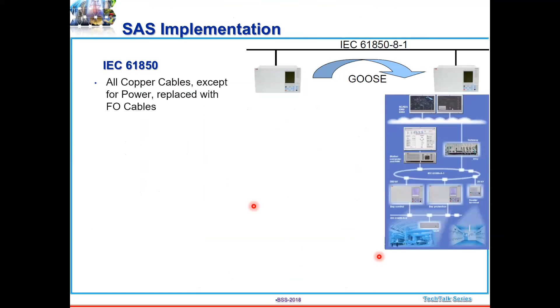In earlier days, we used to have a lot of copper cables coming into the picture. Just a mess. You require more room, more space, more control trenches, cable trenches. Everything should be there. But now, because of this IEC 61850 option, substation automation system implementation, it has come down like anything. We use fiber cables for that, and the space requirement has also come down. The control room requirements have also come down. It has become very modular. All the control equipment has become very modular.